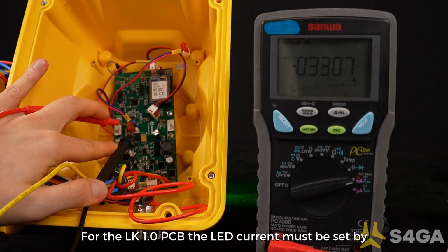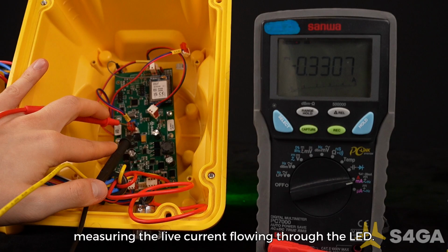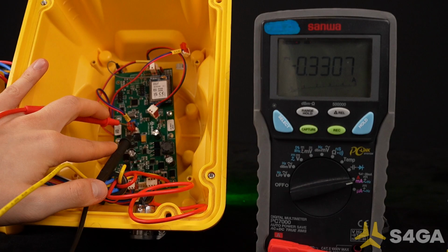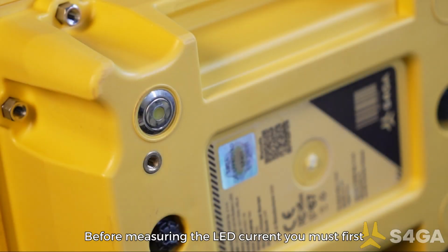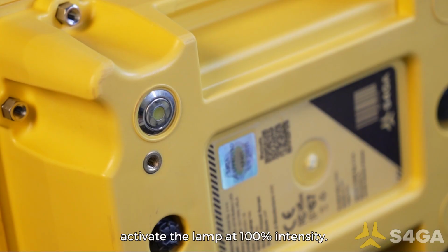For the LK1 PCB, the LED current must be set by measuring the live current flowing through the LED. During this procedure, the lamp must remain turned on. Exercise caution to avoid contact between conductive surfaces. Before measuring the LED current, you must first activate the lamp at 100% intensity.